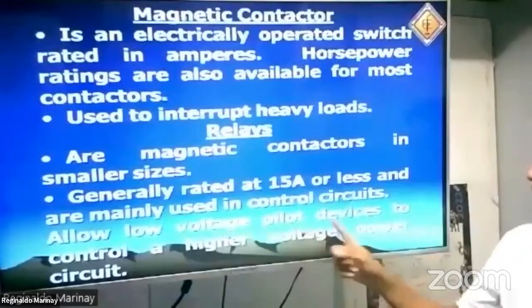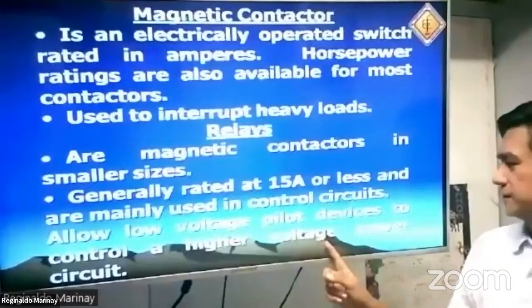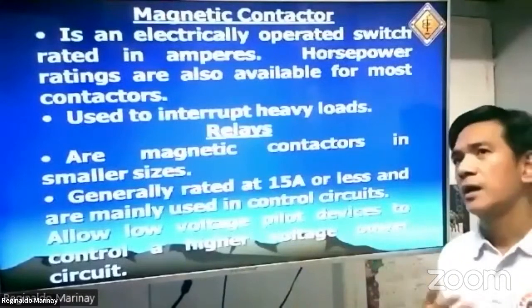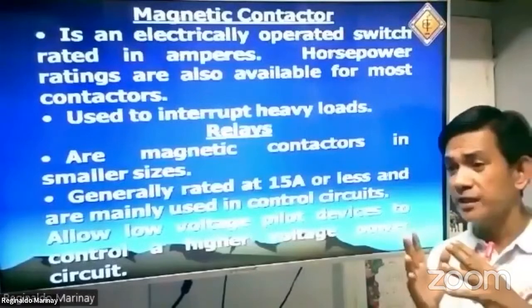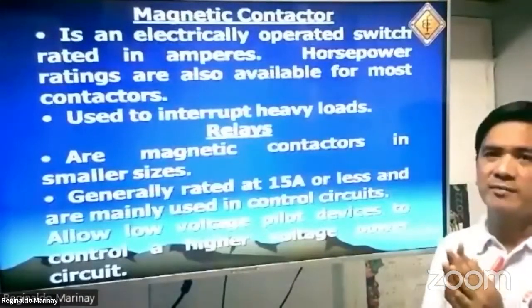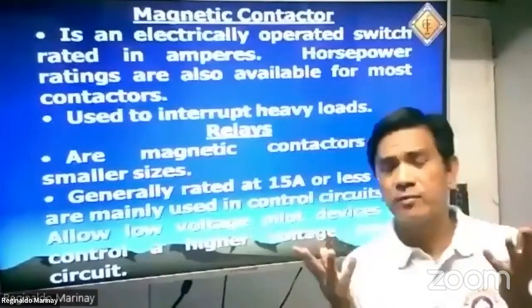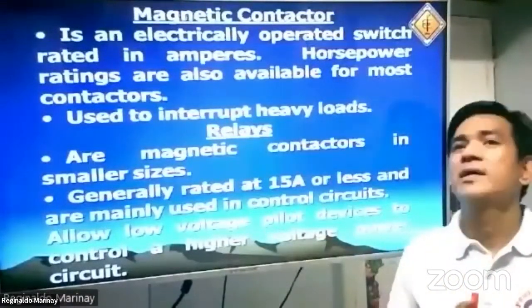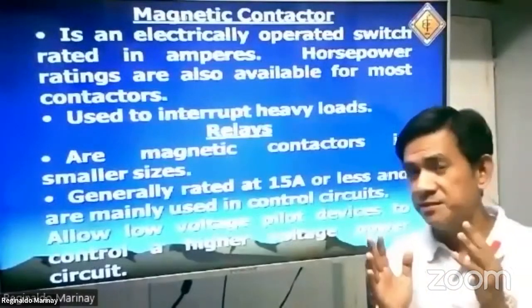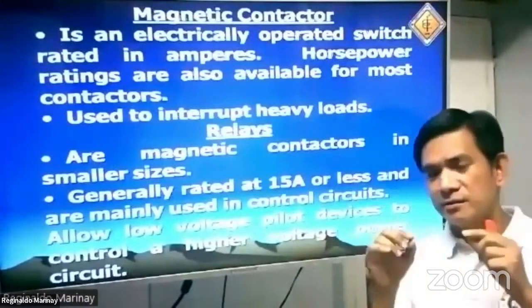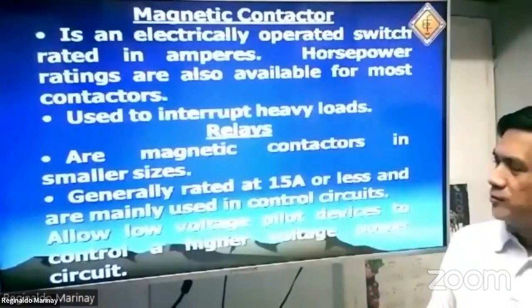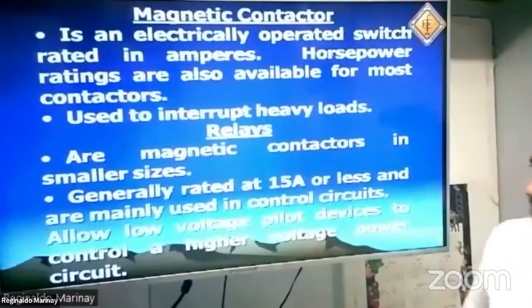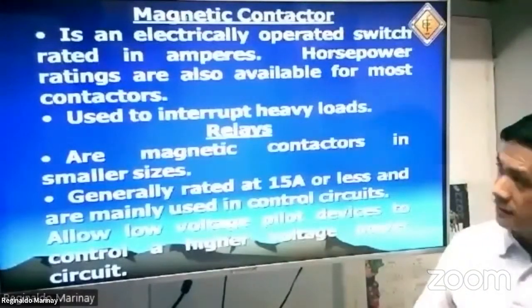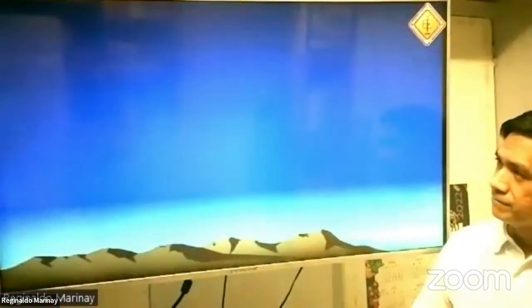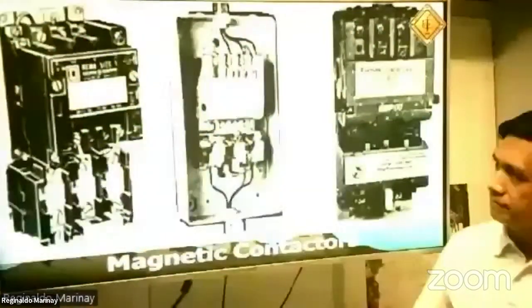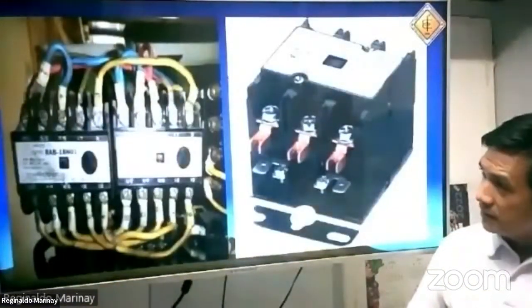So these relays allow low voltage pilot devices to control a higher voltage circuit. And remember, there is a question: can you have a low voltage control circuit? If you have a 230 or 460 volt system, can you have around a 24 volt or 12 volt control circuit for your motor control system? The answer is yes, it can. It's possible by the use of a transformer, wherein you step down the voltage, and you will have some of your motor control devices, also your relays, in the lower voltage. These are sample pictures of the magnetic contactor.